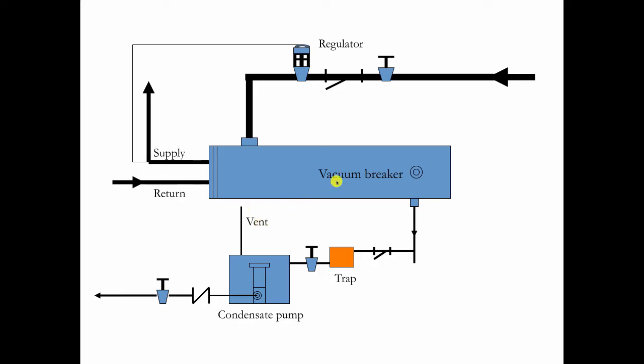Now what's absolutely critical here is this vacuum breaker, which is in the side of the shell. And I say it's critical because when the regulator shuts, the steam beyond the regulator is going to condense and shrink 1,700 times in volume. So you're going to get a vacuum forming inside this.